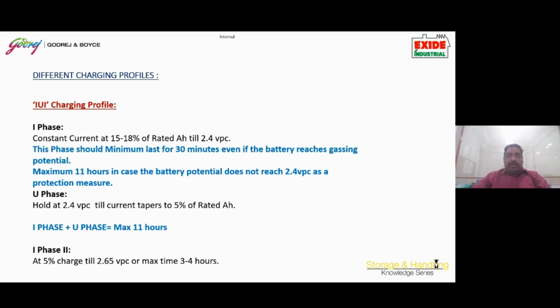Now, why 2.4 volt? 2.4 volt is the voltage where the gassing inside the battery happens. So anything charged beyond 2.4 volt, the battery will start emitting hydrogen gas into the atmosphere at a rate much higher than till it achieves a charge voltage of 2.4 VPC. We don't want the hydrogen to be lost into the air as hydrogen gas, because that's not useful either for the environment or for us. If hydrogen gas goes out of the electrolyte, then we will have to frequently add DM water to compensate for that loss.